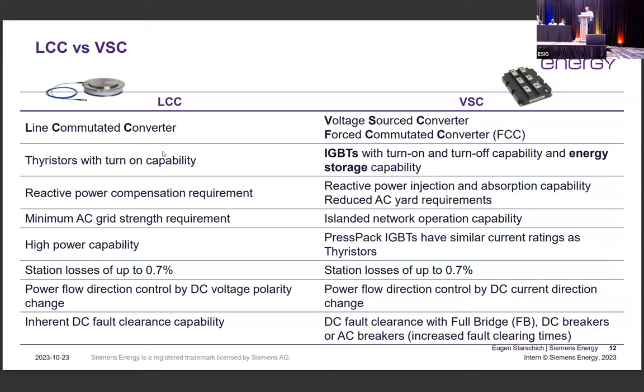One of the big advantages that the LCC still retains is the inherent DC fault clearance capability. That means if we have a DC line fault, it's very easy for the LCC to clear the fault. For the VSC technology, we either need a so-called full bridge setup, which we will talk about a little bit later, or we need DC breakers, or we can do it with the AC breakers. That means we have slightly increased fault clearing times with the AC breakers, but the DC fault clearing capability of the standard VSC technology is not as good as with the LCC.